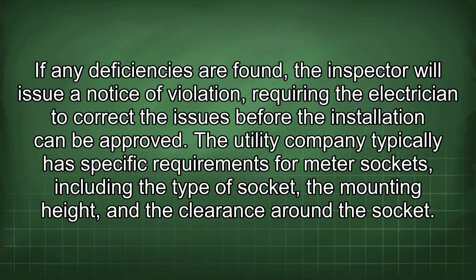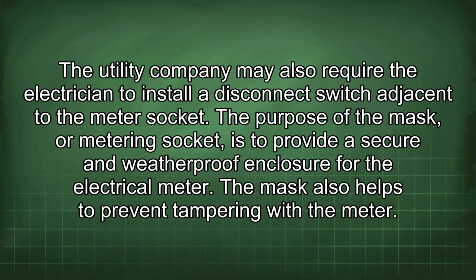The utility company typically has specific requirements for meter sockets, including the type of socket, the mounting height, and the clearance around the socket. The utility company may also require the electrician to install a disconnect switch adjacent to the meter socket. The purpose of the mask or metering socket is to provide a secure and weatherproof enclosure for the electrical meter. The mask also helps to prevent tampering with the meter.